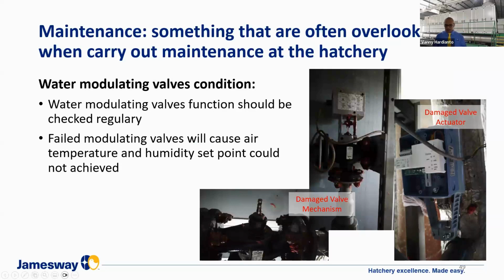And here is the water modulating valve. It is very important also to always check the function of the valve. The actuator or the valve mechanism should always be in good condition. Failure in the modulating valve will cause air temperature and humidity to not reach the set point. And sure, it will affect hatchery performance.